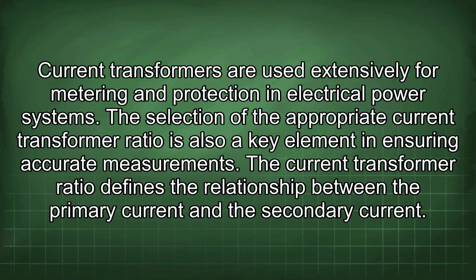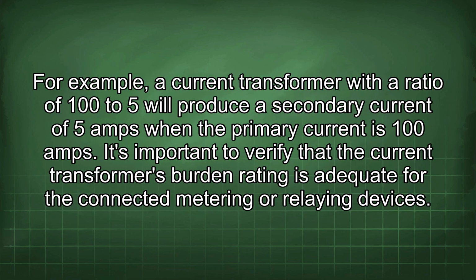The selection of the appropriate current transformer ratio is also a key element in ensuring accurate measurements. The current transformer ratio defines the relationship between the primary current and the secondary current. For example, a current transformer with a ratio of 100:5 will produce a secondary current of 5 amps when the primary current is 100 amps.